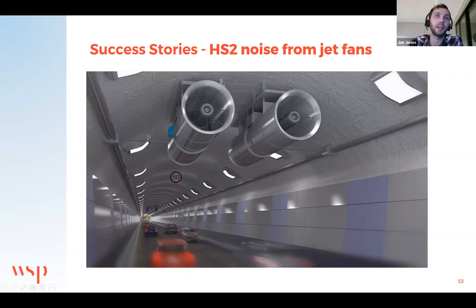The point of them being, as trains entered the station area out of the tunnels, they brought with them a lot of heat. The station doesn't want to have to deal with that amount of heat. So these jet fans blow air against the direction of travel to stop that heat from blowing into the platform area.